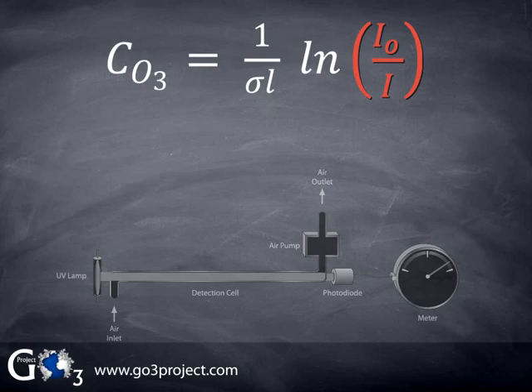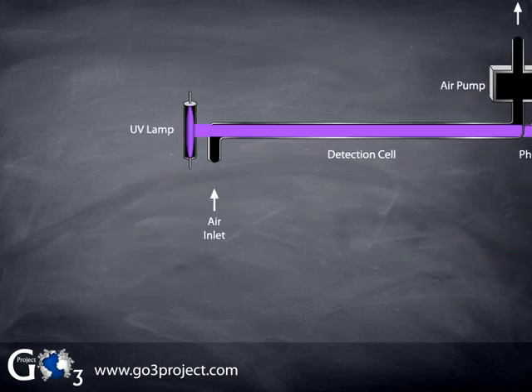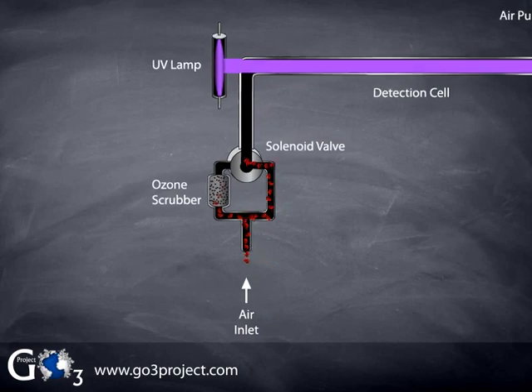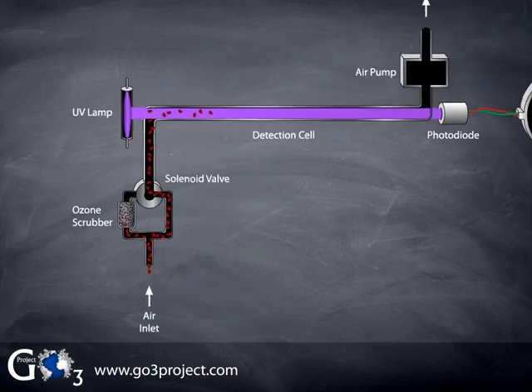So in our instrument, we need a way to alternately measure I and I0. This can be done by using an ozone scrubber to remove ozone and a solenoid valve to alternately switch the air flow between going through the ozone scrubber or bypassing it. The ozone scrubber is made of a material such as hopcalite that destroys the ozone molecules by converting them into ordinary oxygen molecules. A solenoid valve uses an electromagnet to repeatedly switch the flow path between a position where ozone passes through the ozone scrubber and a position where ozone bypasses the ozone scrubber.